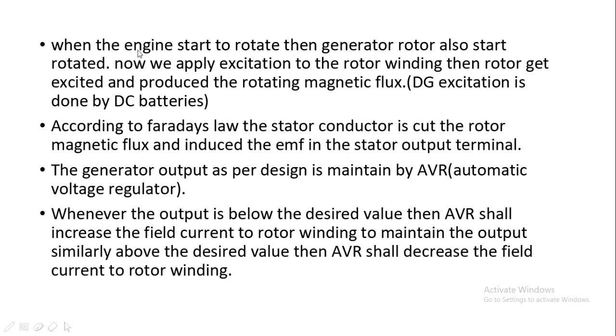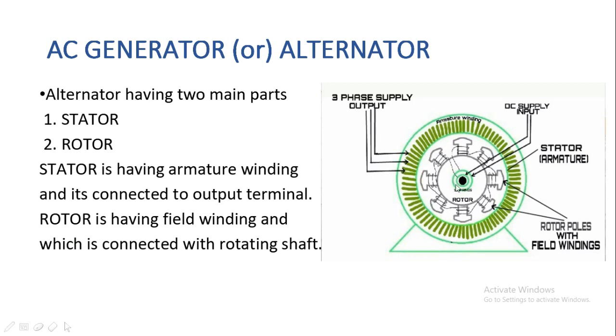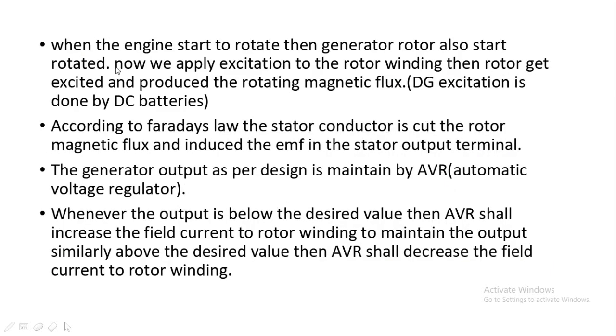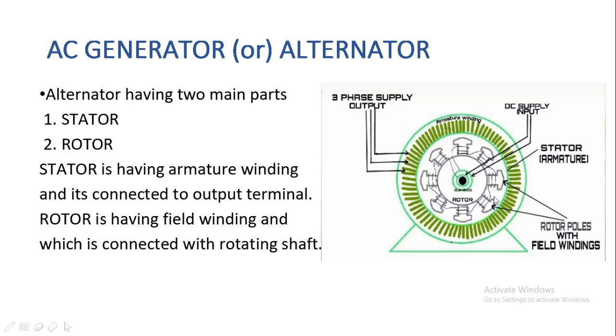When the engine starts to rotate, the generator rotor also starts rotating, since it is mounted on the same rotating shaft. Now we apply excitation to the rotor winding. Excitation means we are giving an external DC supply or DC current to this field winding — through an external battery or similar source — as input supply to the field winding.